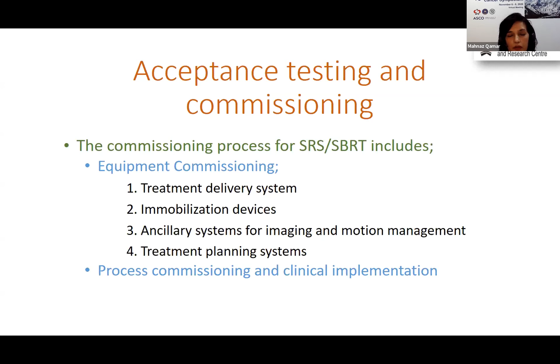So commissioning is performed by physics teams after initial acceptance. Once they get together with the installation engineer and do an initial acceptance testing, then comes the major part that is performed by the physics team, where they establish a baseline characterization of the performance of the system, which then forms the basis of the future QA, the periodic QAs. At that time, they have to define the limitations of the system, depending on what kind of applications it's going to be used for.